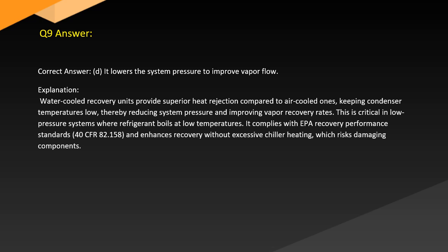Answer. Correct answer: D. It lowers the system pressure to improve vapor flow. Explanation. Water-cooled recovery units provide superior heat rejection compared to air-cooled ones, keeping condenser temperatures low, thereby reducing system pressure and improving vapor recovery rates. This is critical in low-pressure systems where refrigerant boils at low temperatures. It complies with EPA Recovery Performance Standards, 40 CFR 82.158, and enhances recovery without excessive chiller heating, which risks damaging components.